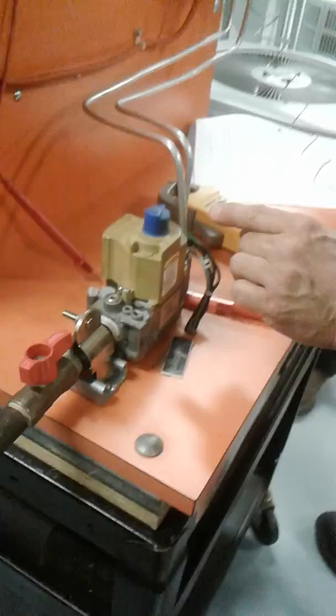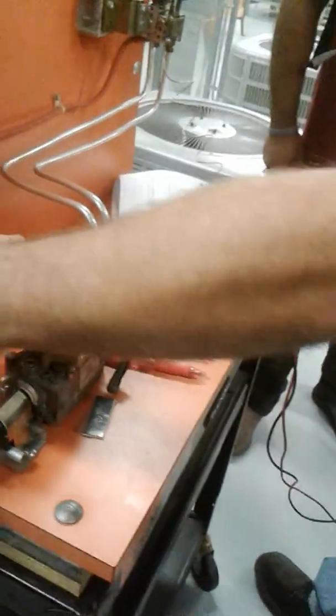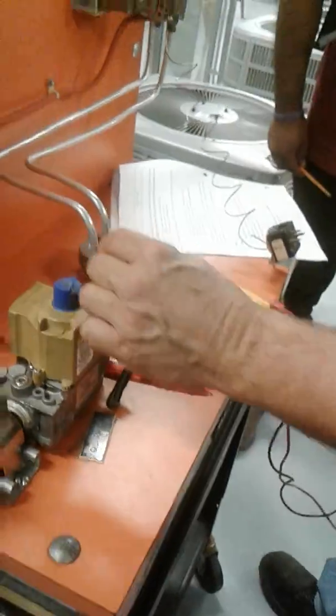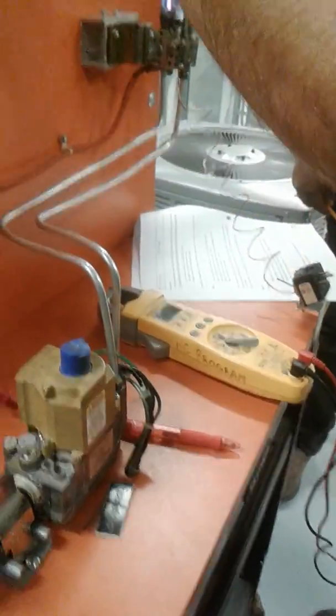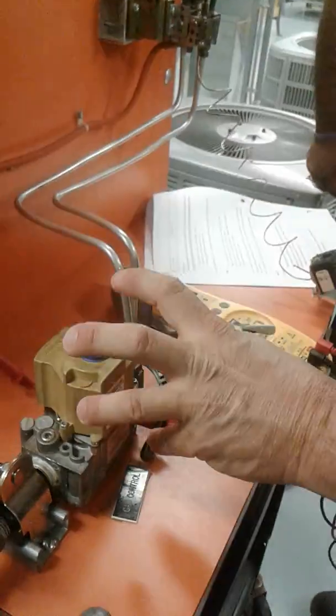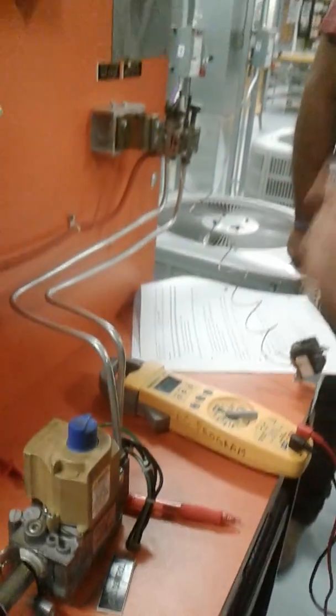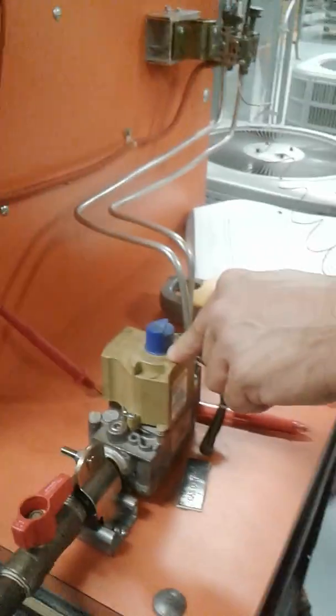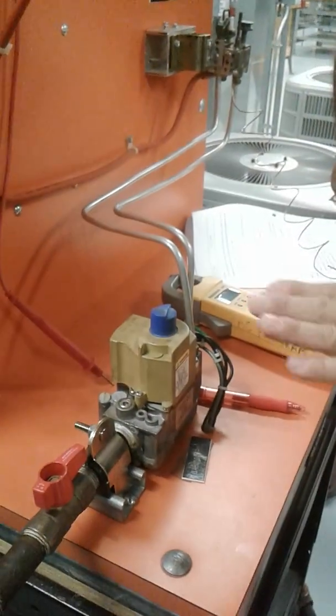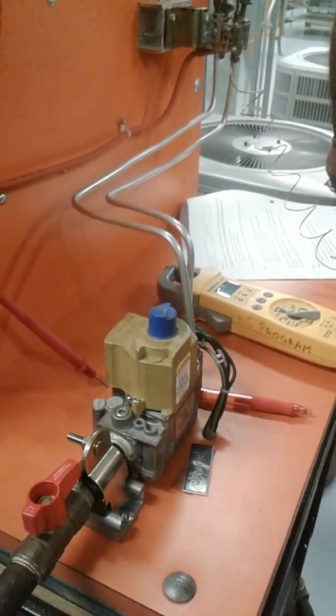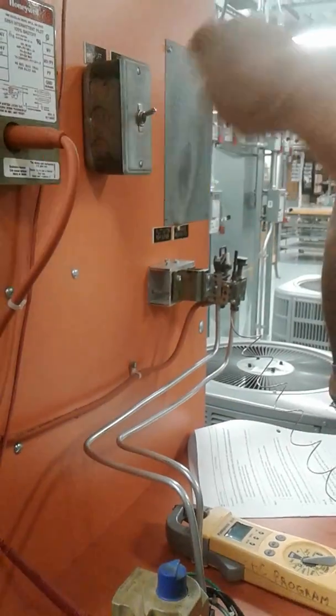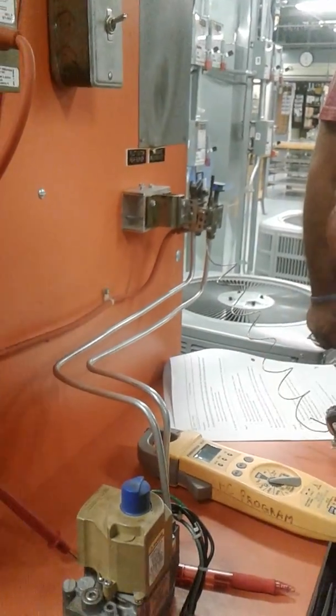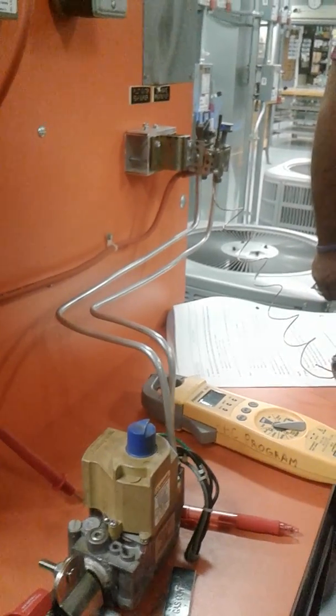Keep in mind, guys, we got to supply 24 volts to our gas valve to energize the coil inside to open up and allow the gas to flow. Once we take the voltage away, the power goes away and the valve closes just like that, because this is a normally closed valve, okay? Once you take the power away or it fails or the coil burns out, it kills itself, it dies, okay? And it's supposed to. We give it 24 volts, it opens up. It lights the pilot, then it lights the burner, and we're good to go.